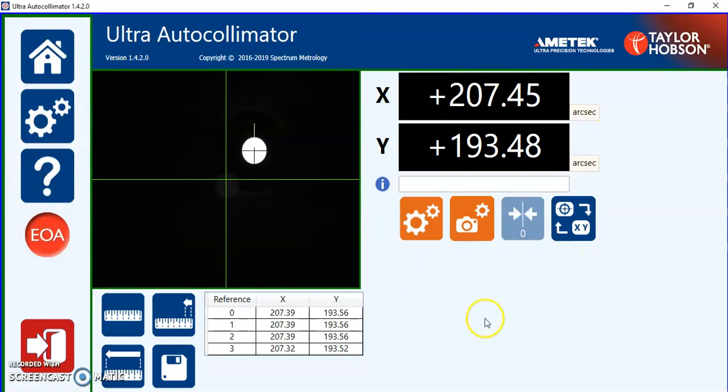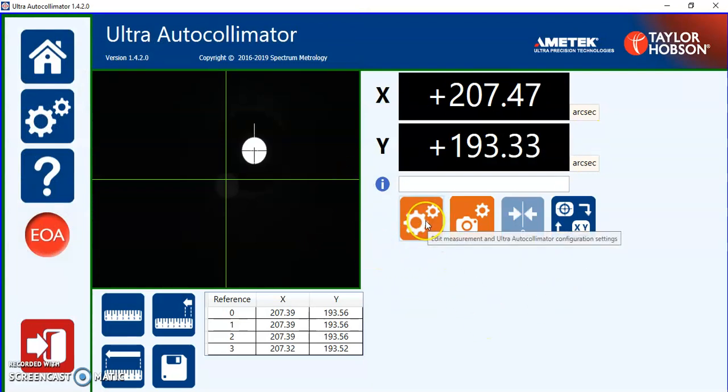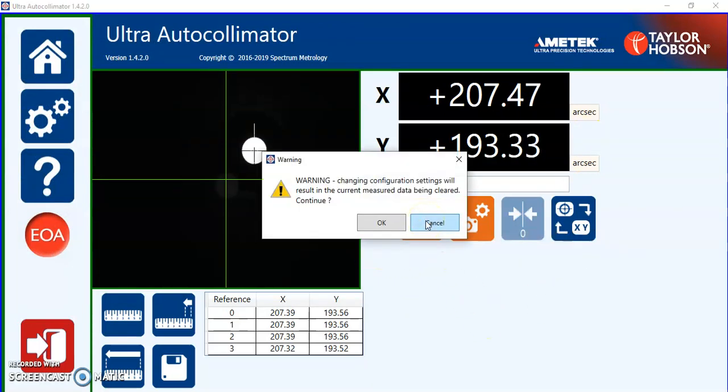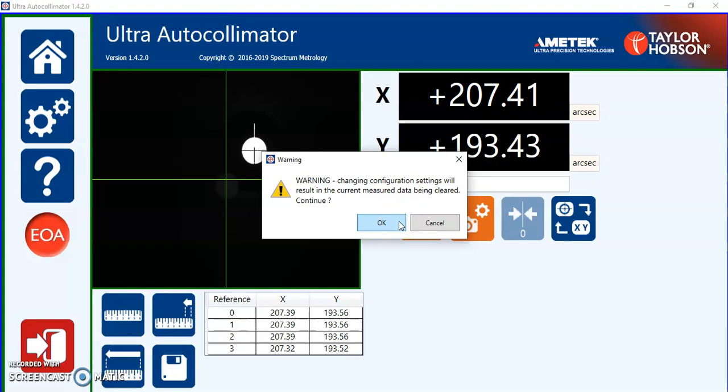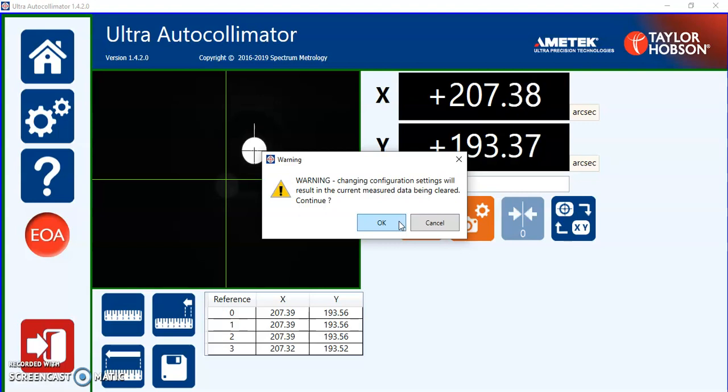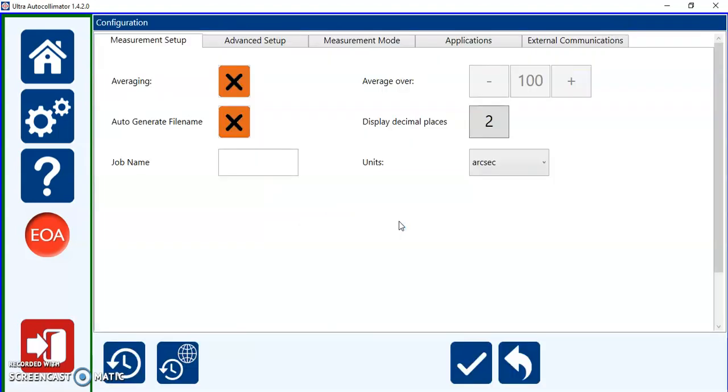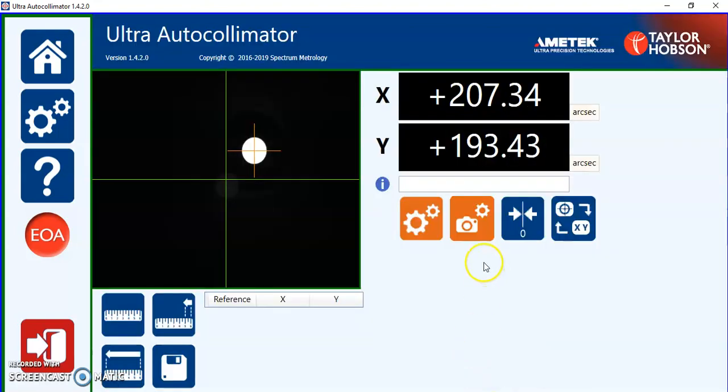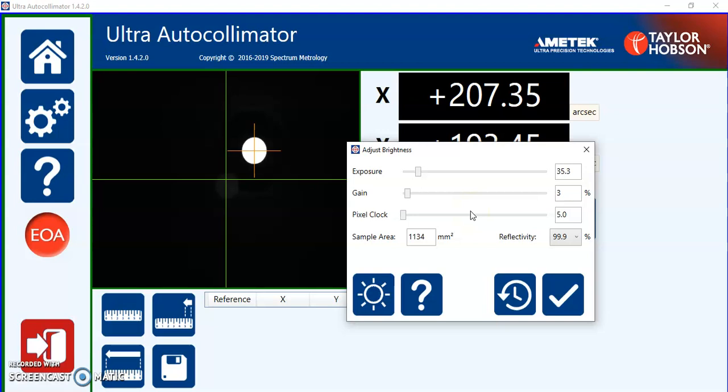On the right hand side we have the ability to change the settings. As soon as I try and do that because we have data it may be that we're going to change measurement conditions halfway through a measurement which is not allowed. So it's warning you it will clear all of the current data if you proceed. So we will proceed. These tabs are all covered in a separate video and are various measurement options. The camera itself you're allowed to adjust the exposure the gain and what's called the pixel clock rate or it can be done automatically and we'll cover this in a separate video.